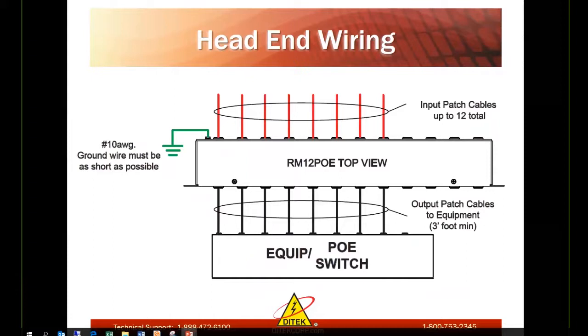Also on that RM12 PoE, we show you up in the upper left-hand corner a ground wire, which needs to be grounded, and it should always be grounded to the same common ground as the equipment you're protecting. So we don't run into any type of ground loop or differential in ground potential, so we keep the grounds common.